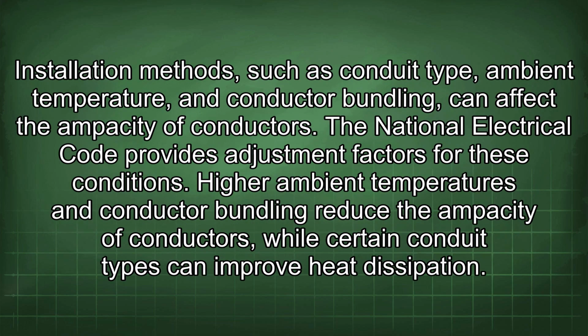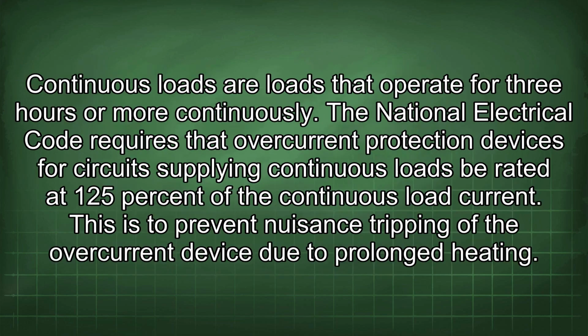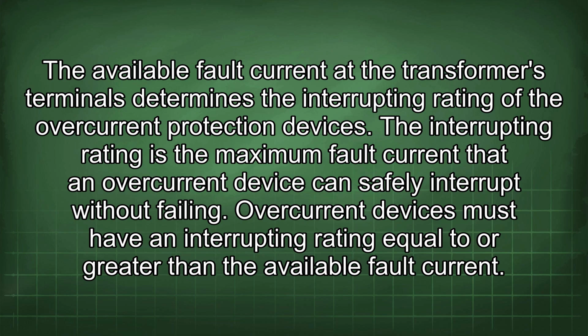Installation methods, such as conduit type, ambient temperature, and conductor bundling, can affect the ampacity of conductors. The National Electrical Code provides adjustment factors for these conditions. Higher ambient temperatures and conductor bundling reduce the ampacity of conductors, while certain conduit types can improve heat dissipation. Continuous loads are loads that operate for 3 hours or more continuously. The National Electrical Code requires that overcurrent protection devices for circuits supplying continuous loads be rated at 125% of the continuous load current. This is to prevent nuisance tripping of the overcurrent device due to prolonged heating. The available fault current at the transformer's terminals determines the interrupting rating of the overcurrent protection devices.